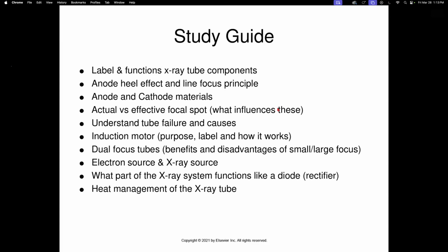So then my attention went where it shouldn't have gone, right? The reason I'm bringing this up is ideally we want the electrons to flow from where to where? Think of that, my attention. Where should it go? Where should the electrons go? From cathode to anode. Okay, fantastic. So with arcing that can cause tube failure, it's going elsewhere because why does it go from cathode to anode?